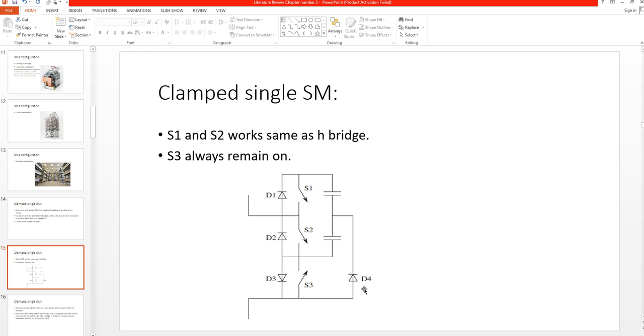Now, if a stiff DC fault occurs on the DC side, two times the rated DC voltage is available for blocking AC side currents flowing from one phase on the AC side through the fault on the DC side and back to another phase. If the arm current is negative, the path for the current is through D2 and D4.